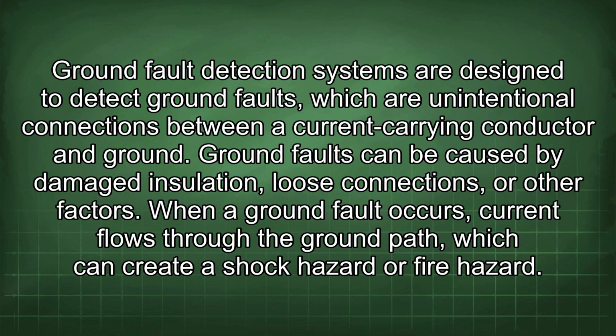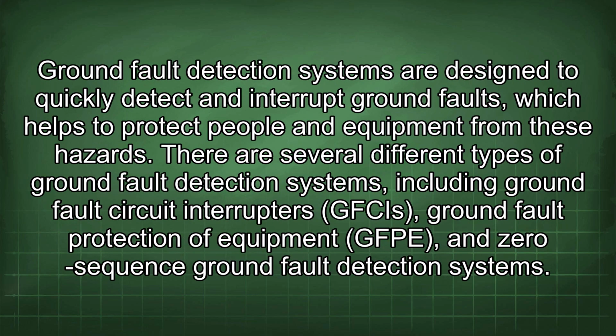Ground fault detection systems are designed to detect ground faults, which are unintentional connections between a current carrying conductor and ground. Ground faults can be caused by damaged insulation, loose connections, or other factors. When a ground fault occurs, current flows through the ground path, which can create a shock hazard or fire hazard. Ground fault detection systems are designed to quickly detect and interrupt ground faults, which helps to protect people and equipment from these hazards. There are several different types of ground fault detection systems, including ground fault circuit interrupters (GFCIs), ground fault protection of equipment (GFP), and zero-sequence ground fault detection systems.